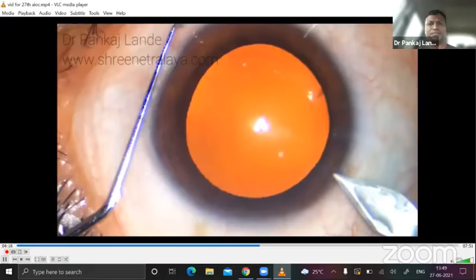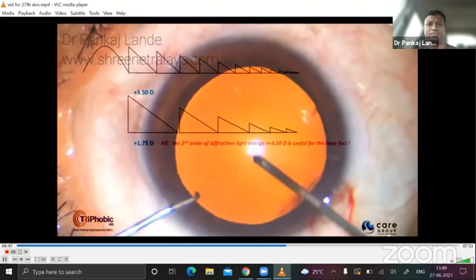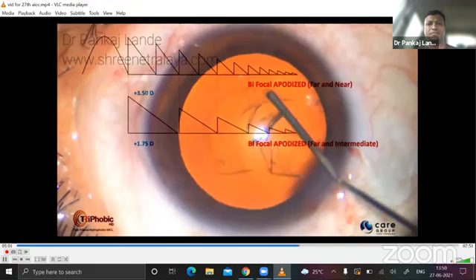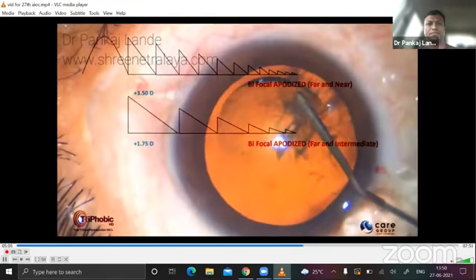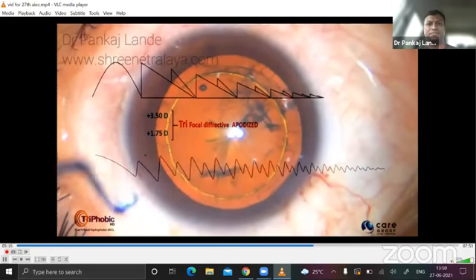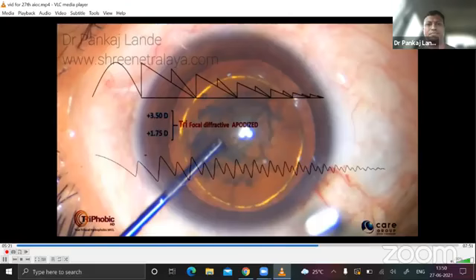Now let's look at how the trifocal IOL is designed. The concept of apodization means a gradual transition of optical properties from the center of the lens to the edge. To apodize the surface, you have to reduce the height of each step, which causes a progressive shift of light energy split towards far focus when the pupil dilates. Consider two apodized diffractive elements — one for far and near, the other for far and intermediate. We adjust the height of diffractive steps to split energy optimally between the near, far, and intermediate foci. The combined diffractive pattern has a near add of +3.5 and +1.75 combined, and each step height is decreased towards the apodized surface.